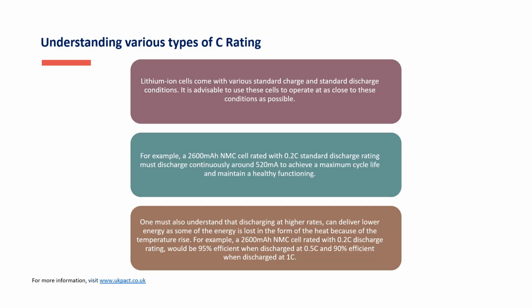For example, let's take a popular cell being imported from China into India, very popular in electric two-wheeler scooters - a 2600 mAh NMC cell in 18650 form factor. Most of the time it has a standard discharge rating of 0.2 C. This means it must discharge continuously around 520 milliamps per cell to achieve maximum cycle life and maintain healthy functioning.